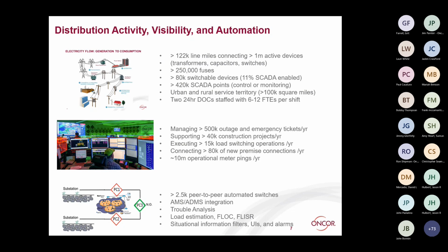What I want to point out, on the Oncor distribution system we have about 80,000 switchable devices. Those have the capability to reroute the power flow. But here's the point, that's where we are in that transformation, in that transition. Historically, 20 years ago, I'd say all of those 80,000 probably didn't have any SCADA. They were totally dark, nothing. Somebody has to go out there and manually operate that switch, either with a stick operating up on the pole or through a crank handle at the bottom. That's literally how we operate these devices.